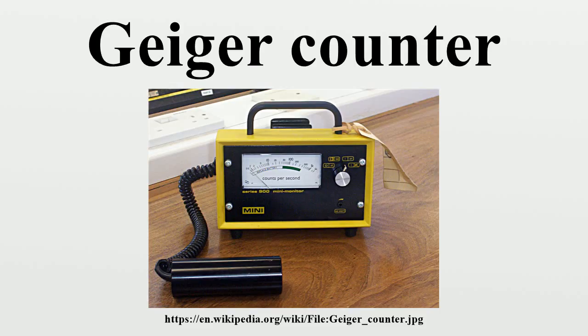Gamma measurement, personnel protection and process control. The term Geiger counter is commonly used to mean a handheld survey-type meter. However, the Geiger principle is in wide use in installed area gamma alarms for personnel protection, and in process measurement and interlock applications. A Geiger tube is still the sensing device, but the processing electronics will have a higher degree of sophistication and reliability than that used in a handheld survey meter.